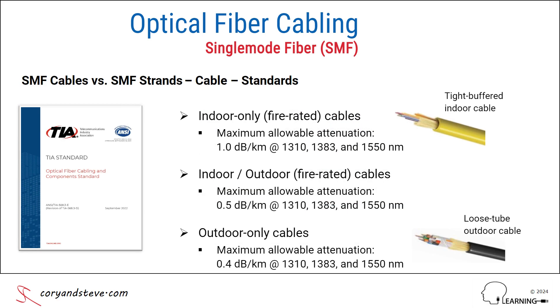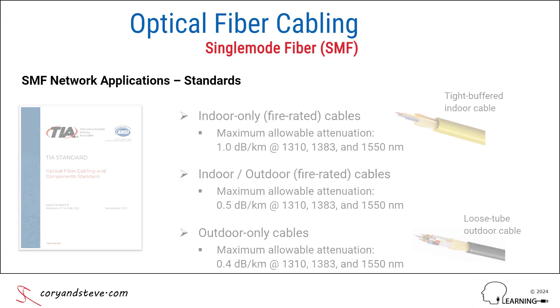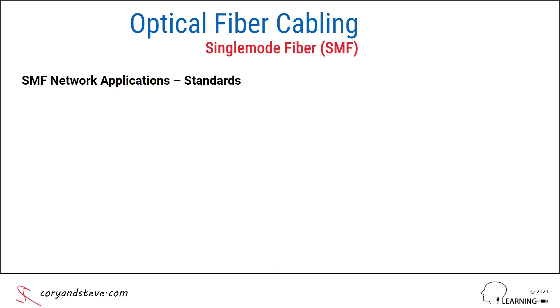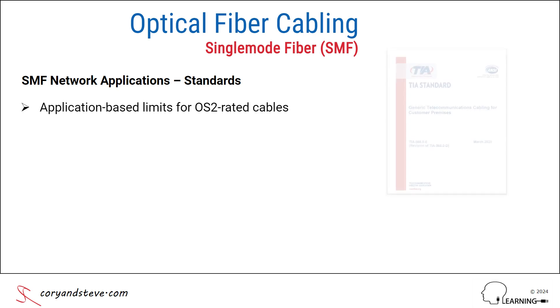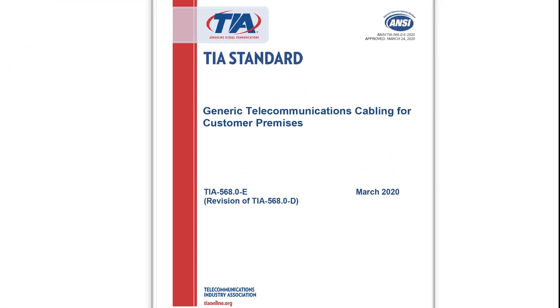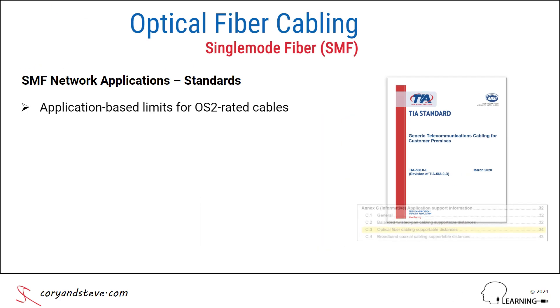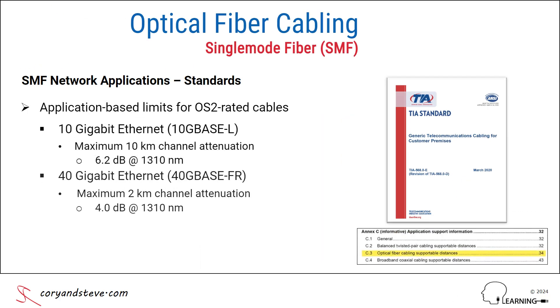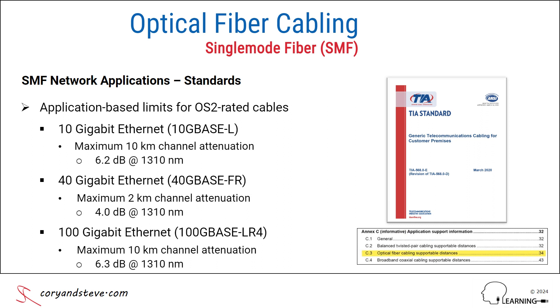The last type of standard to review is for the network applications that operate over the OS2-rated cables. The maximum allowable length of OS2-rated cable between two network devices depends on the application or type of network, so the cabling system designer needs to consider both current and expected future requirements. The TIA-568.0 standard, currently in Edition E, lists the supportable distances and maximum allowable end-to-end channel attenuation values for various types of networks, including 10, 40, and 100 Gigabit Ethernet.